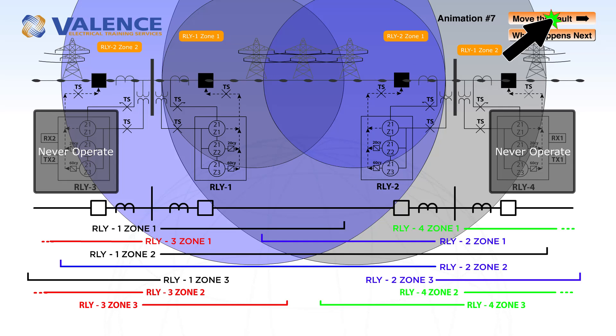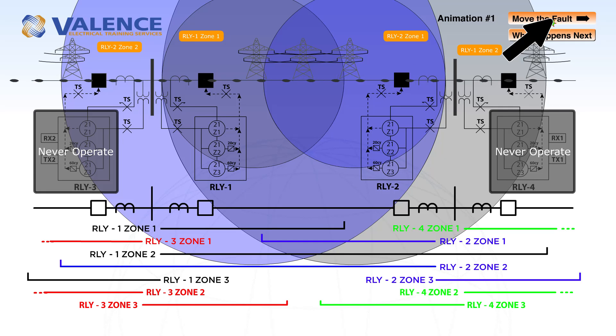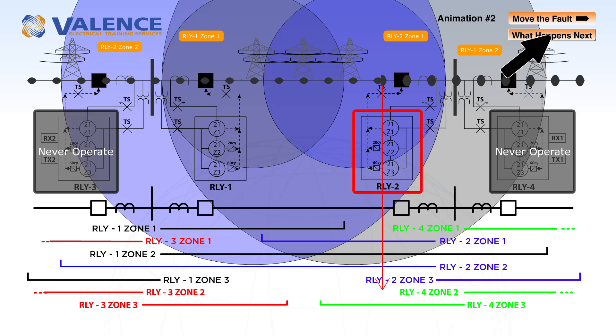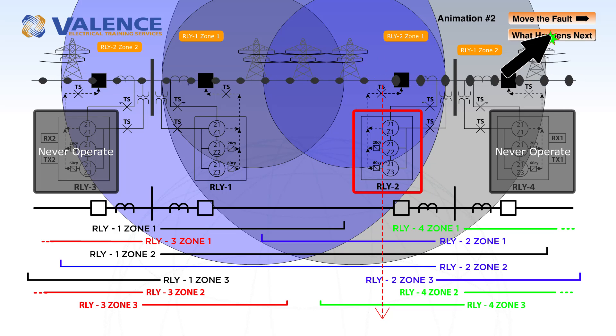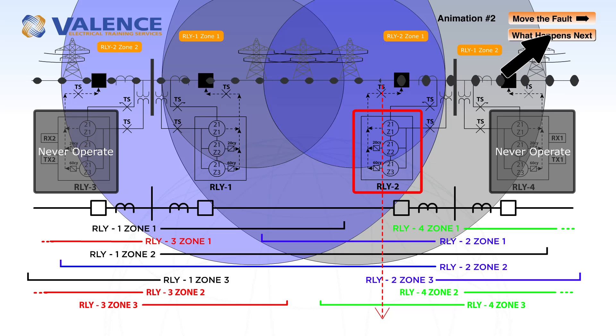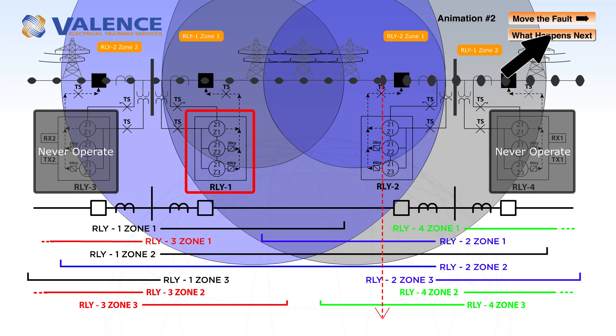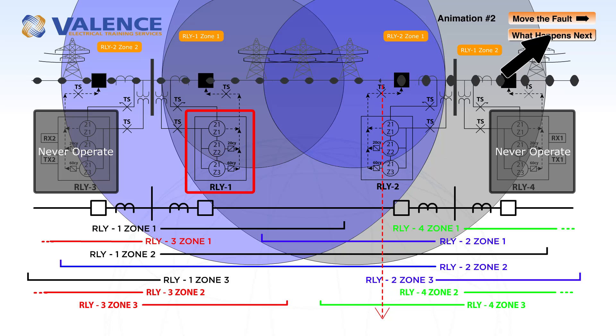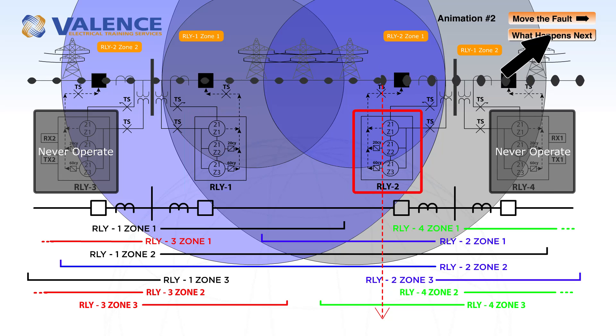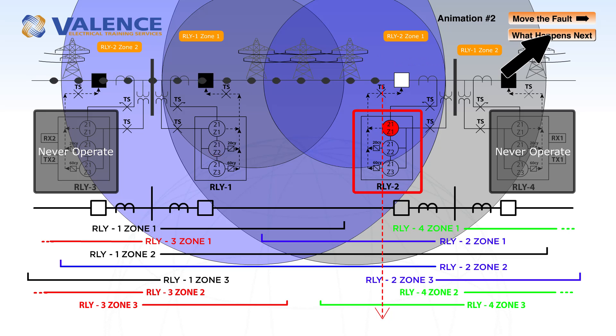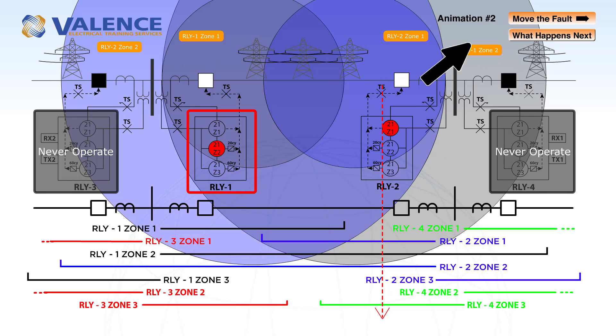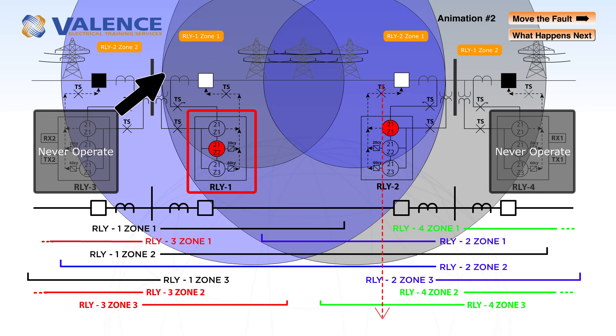If we move the fault a little bit closer to relay 2, we can see that relay 2 is going to detect a zone 1 and zone 2 pickup, but relay 1 is only going to detect a zone 2 fault. So relay 2 is going to operate almost instantaneously on zone 1, and relay 1 is going to operate about 20 cycles later.